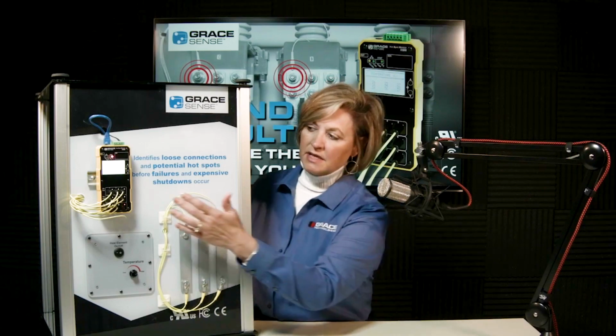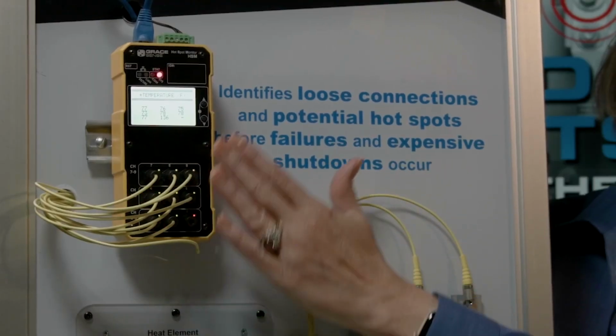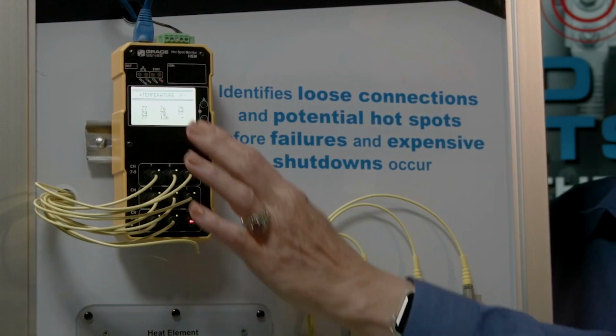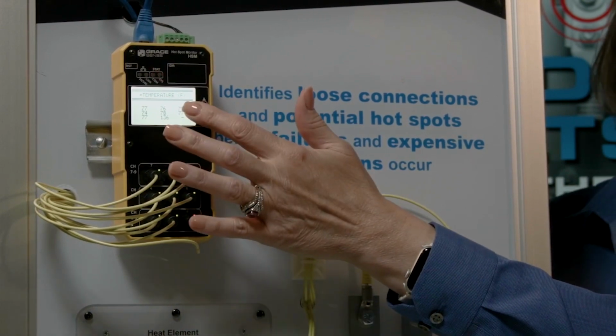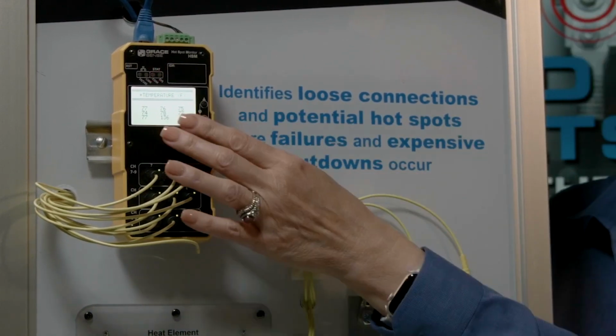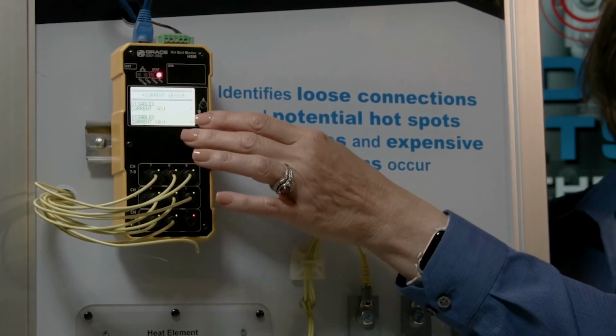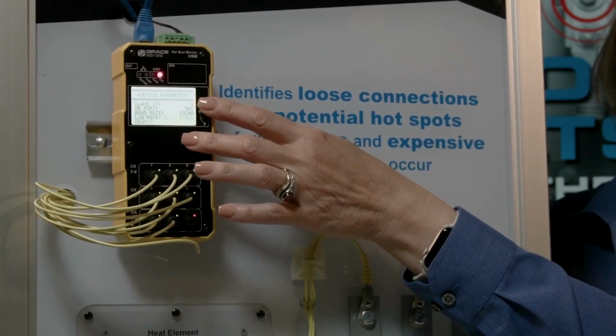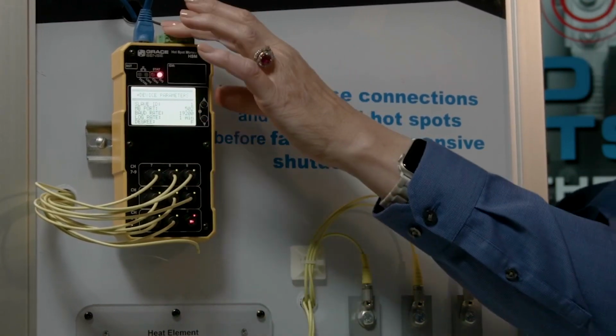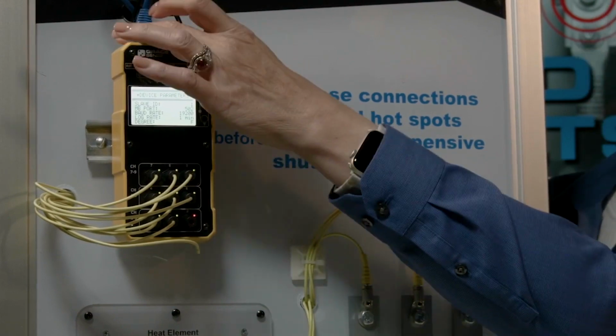So the module itself comes in either 9 or 18 points. The 9 has an LCD display screen, so you can see the temperature and you can scroll through all the different values and settings inside of it. It has an Ethernet cable, so either Modbus TCP, RTU, or Ethernet IP as a protocol to go to a power management system or an existing DCS, for example.